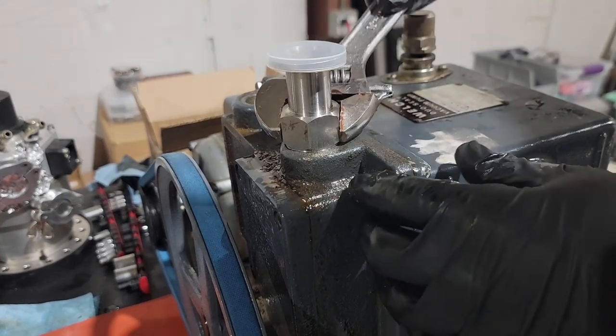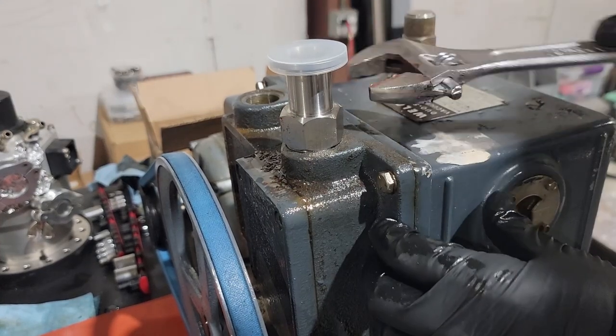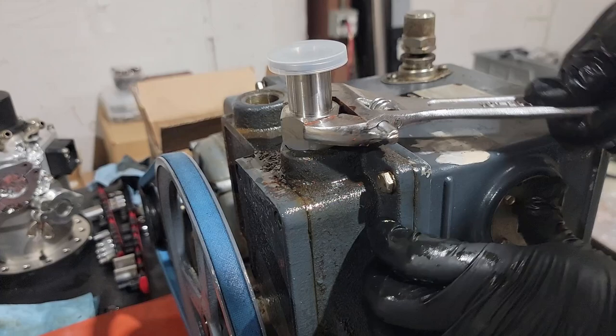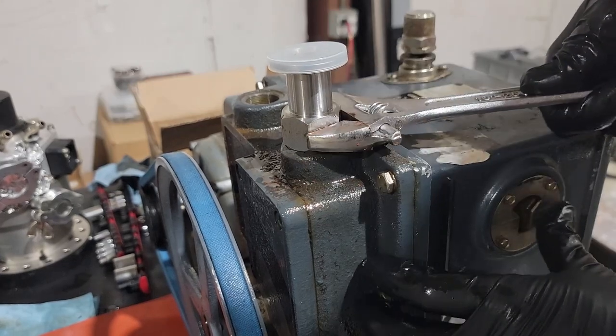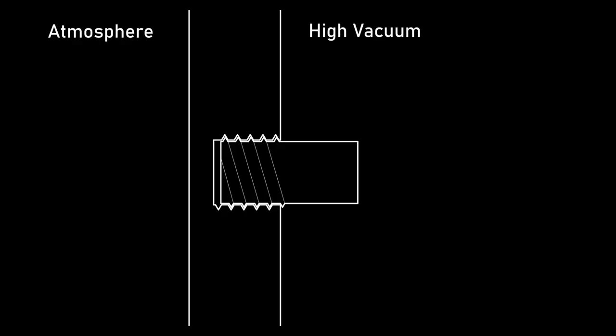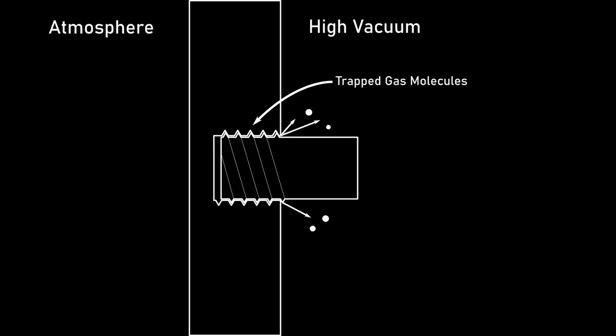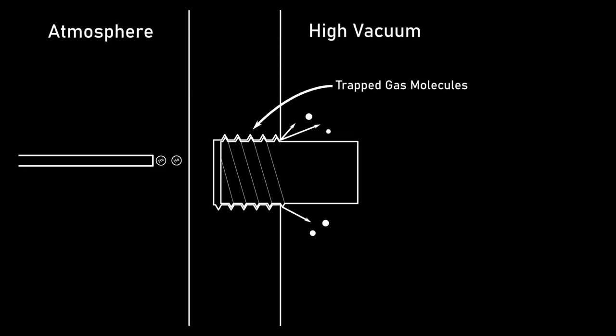In general, you should avoid threaded fittings in vacuum systems, not only because they're hard to seal against actual leaks, but because they present the possibility of virtual leaks. A virtual leak is where gas becomes trapped somewhere in the vacuum system, such as between the threads of a threaded fitting, and then slowly diffuses out over the course of days or even weeks. These look like leaks and they act like leaks, degrading the vacuum in your system. Unfortunately, they can't be found using any of the usual leak detection methods, so they're a real pain to diagnose.